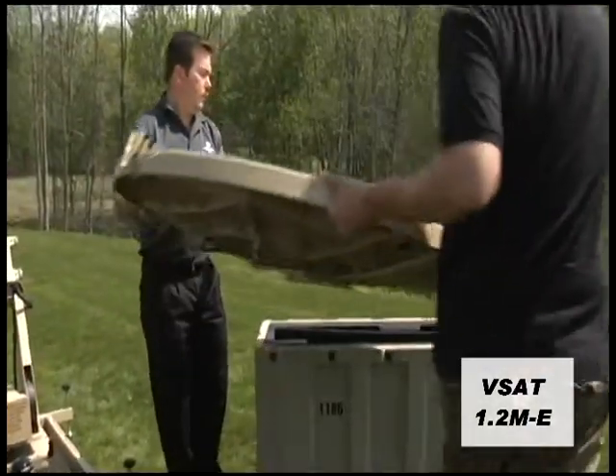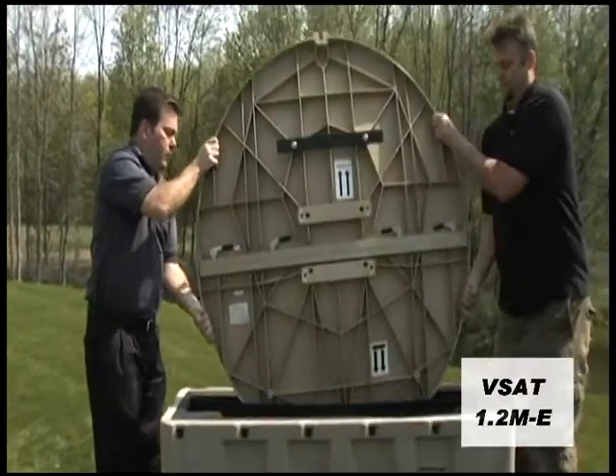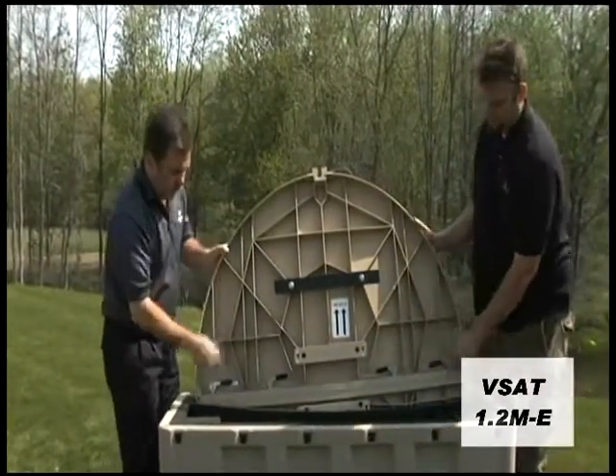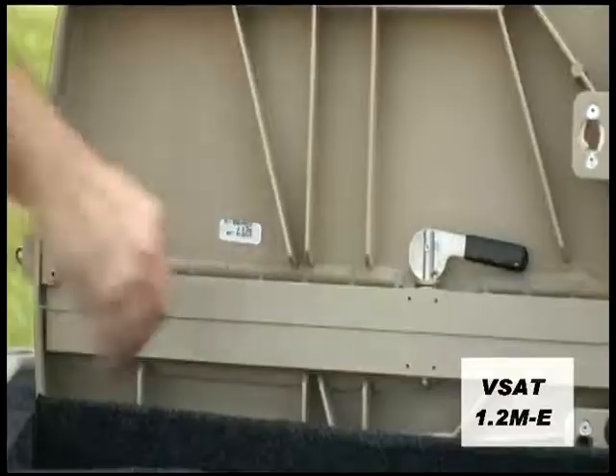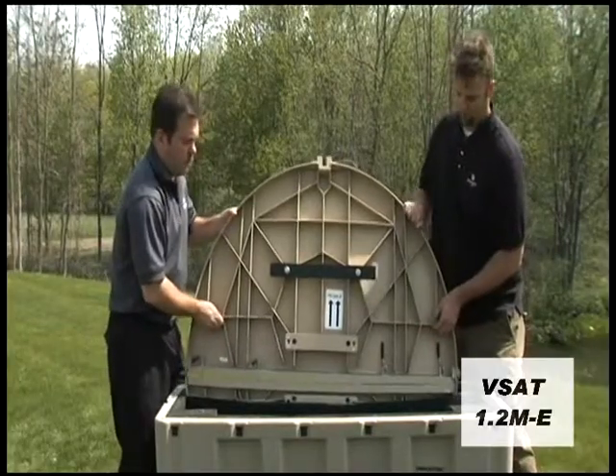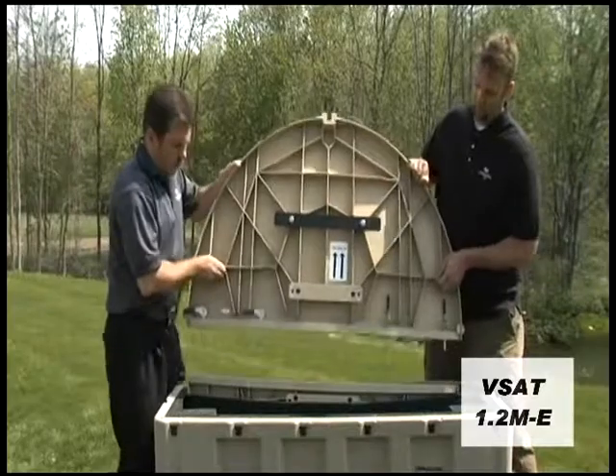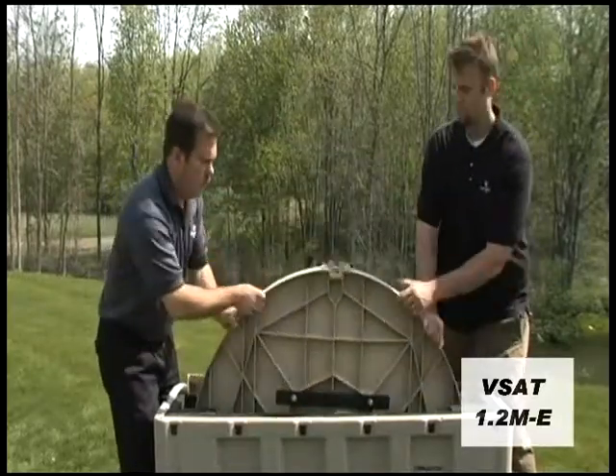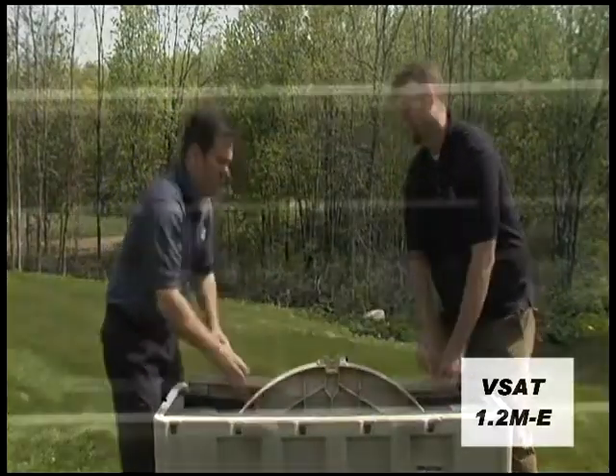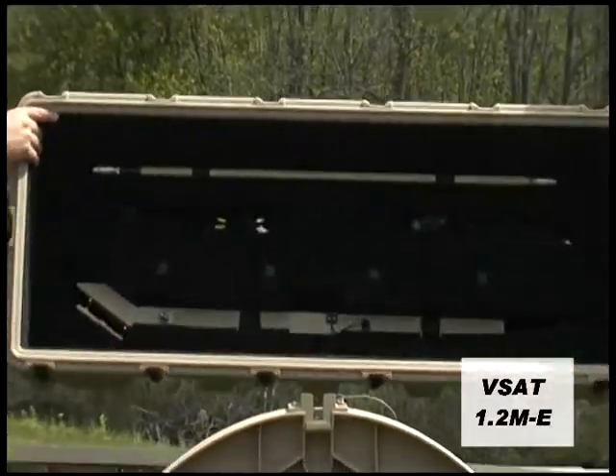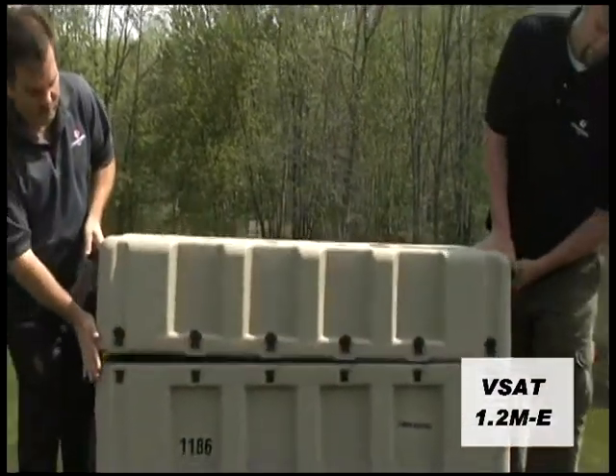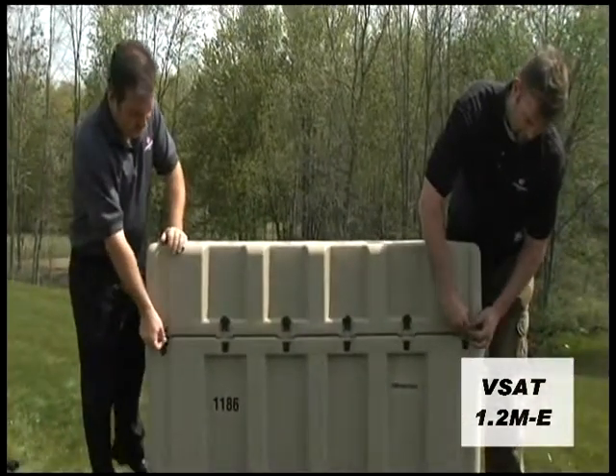Place the complete reflector into the case, bottom half first, the side opposite the black metal brace. Separate the 2 halves of the reflector using the 4 quick-release levers. Place the top half into the case with the round side of the reflector facing up. Be sure all the Velcro securing straps are attached and tight. Replace the lid and secure all latches.